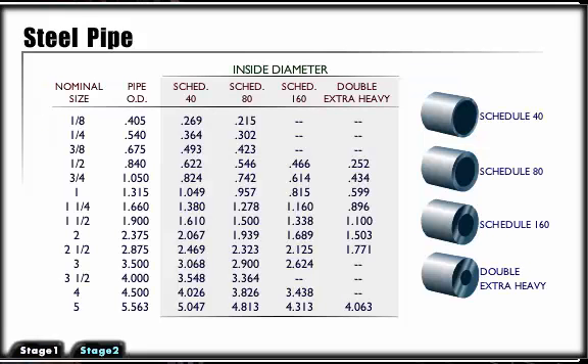Pipe is specified by its nominal outside diameter, but its actual flow capacity is determined by its inside area. For example, schedules 40, 80, and 160 and double extra have the same outside diameter (OD) and can be threaded by the same pipe die. The difference is the inside diameter (ID) and area.